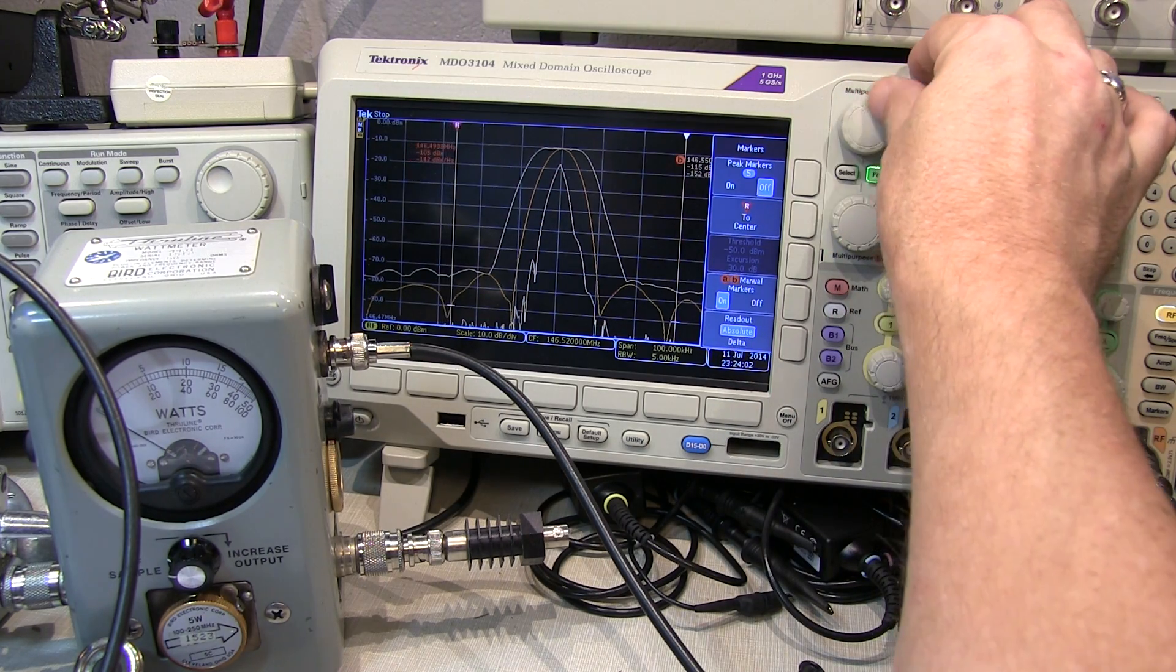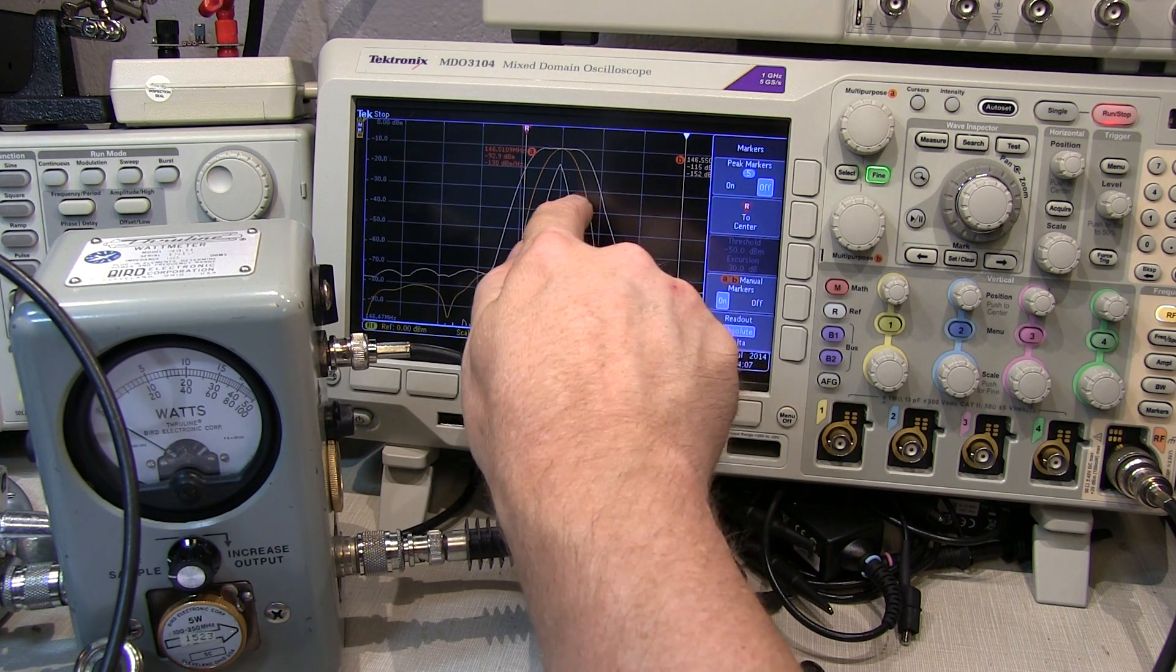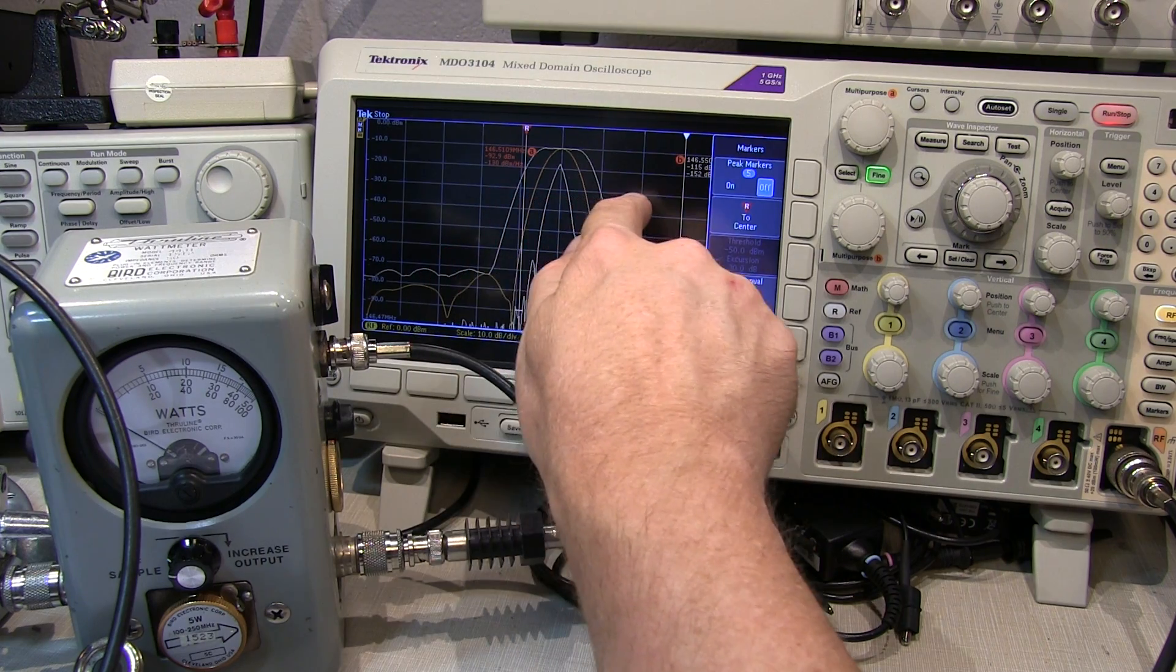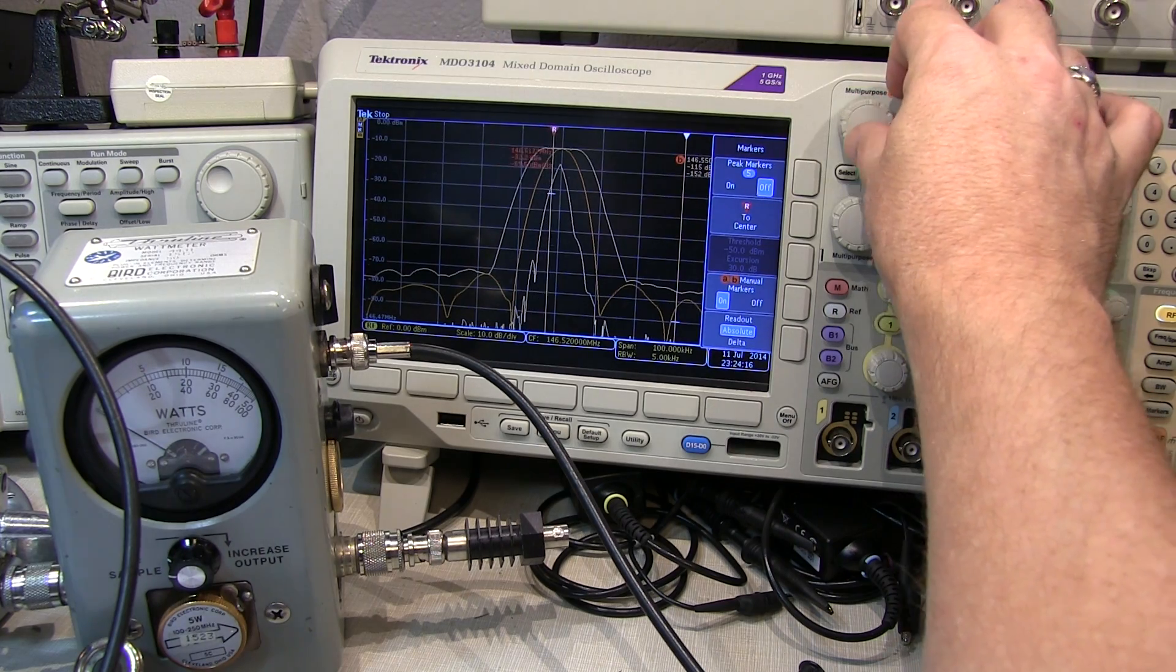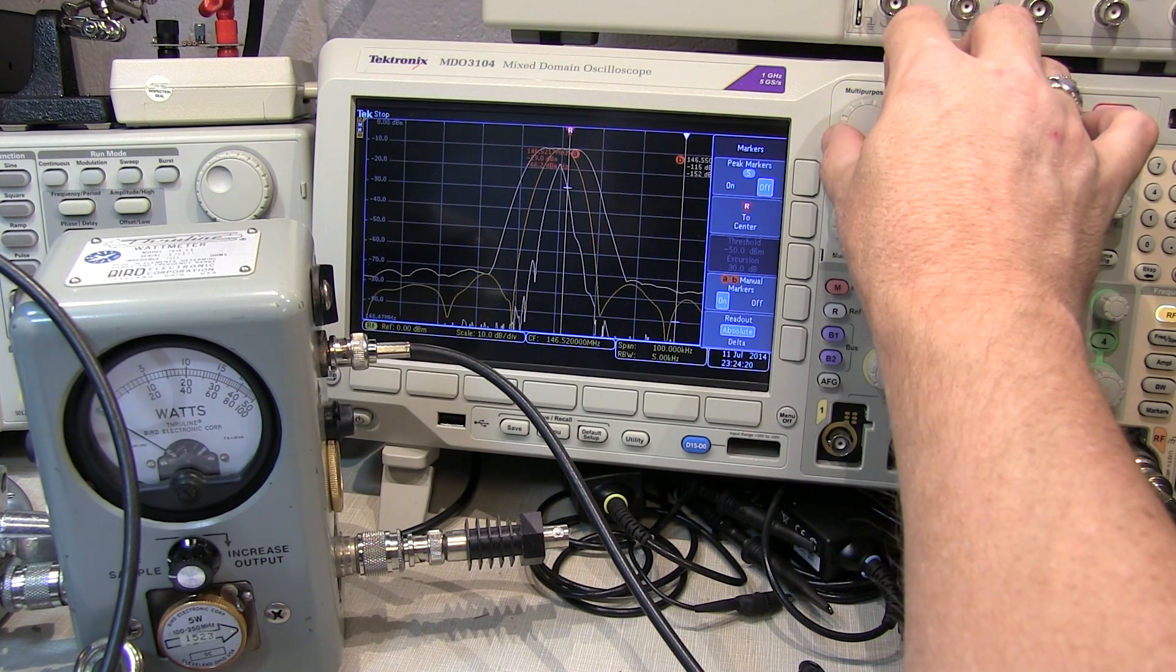What I'll do is move those manual markers to measure the distance from the min hold trace to the max hold trace along a common power level. Let's pick this minus 30 dBm level and move this marker over here until we're right at that crossing level. It's right about there.